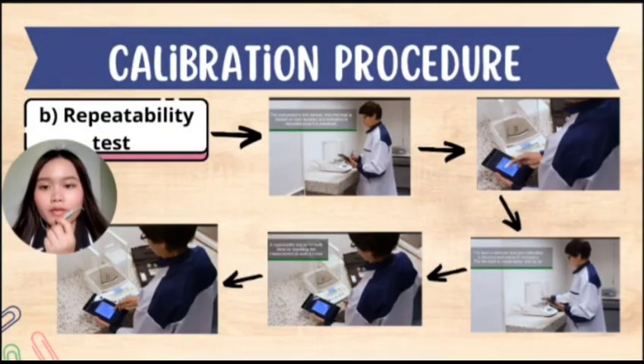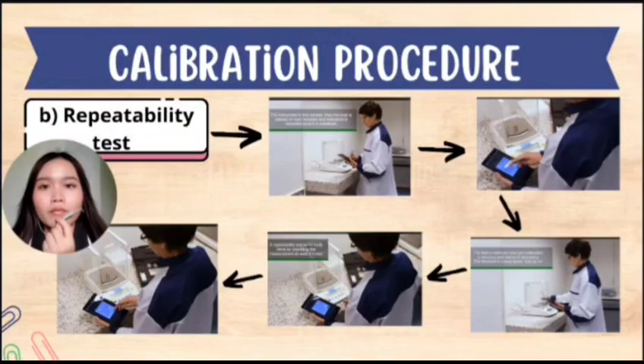Next, we have the repeatability test. When the same load is measured several times, the result is not always exactly the same. Now, to find out the repeatability of the instrument, a repeatability test is done. In this procedure, the instrument is first zeroed, then the load is placed on the load receptor and the indication is recorded once it is stabilized. Next, the load is removed and the zero indication is checked and zeroed if necessary. The load is placed again and so on. A repeatability test is normally done by repeating the measurement at least 5 times.